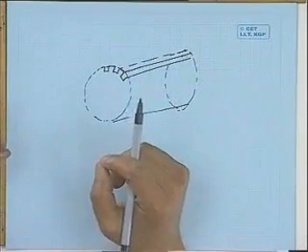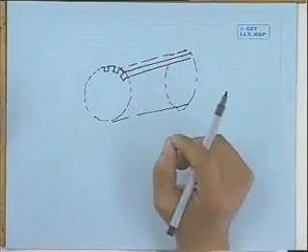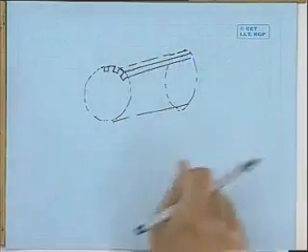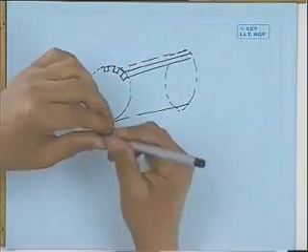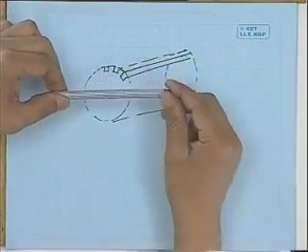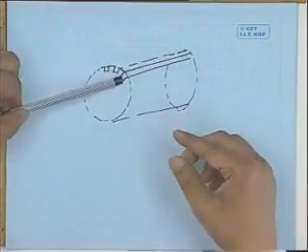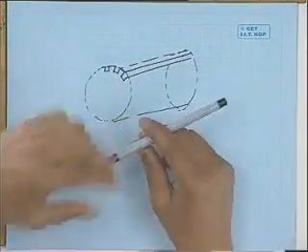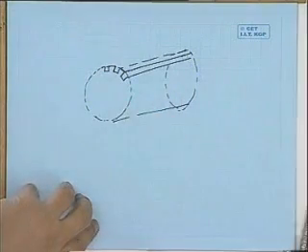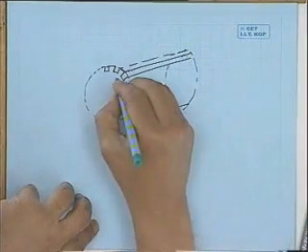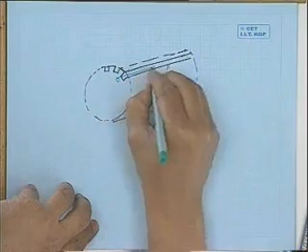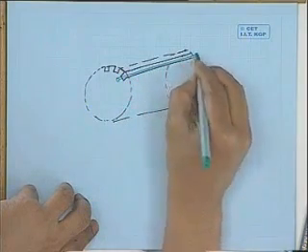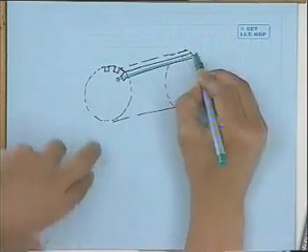Now what is done is this: you imagine that in each slot a solid conductor is inserted, say an aluminum or copper bar. Not in the form of flexible copper wire, you do not make the winding like that. You imagine this one is an aluminum bar, and you just insert it in this slot. So each slot is filled by an aluminum or copper conductor all along the length.